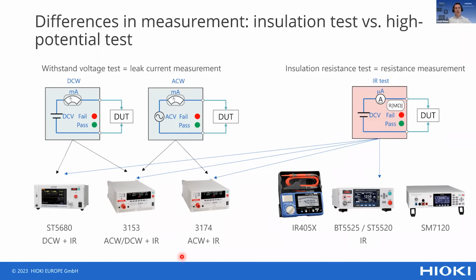All of those 3 also come with an insulation resistance test capability, but please be aware that the insulation resistance values you are getting here are much higher than we have here with the insulation resistance tester, which are specifically for testing the low resistance values here, the high resistance values here. What you can see, we have BT5525 and we have ST5520 as insulation resistance tester, and SM7110 or 20, depending on the applied voltage, and also one portable device.